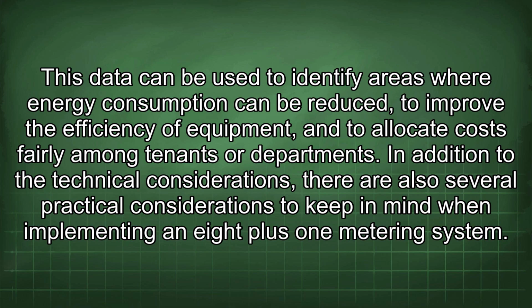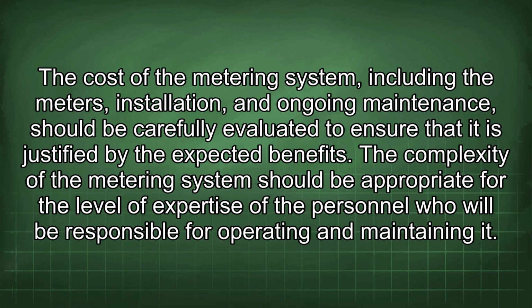In addition to the technical considerations, there are also several practical considerations to keep in mind when implementing an 8+1 metering system. The cost of the metering system, including the meters, installation, and ongoing maintenance, should be carefully evaluated to ensure that it is justified by the expected benefit. The complexity of the metering system should be appropriate for the level of expertise of the personnel who will be responsible for operating and maintaining it.